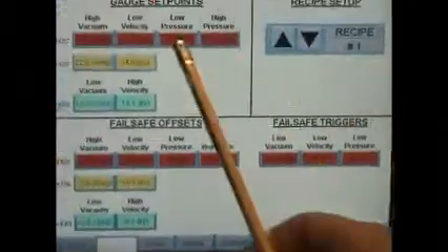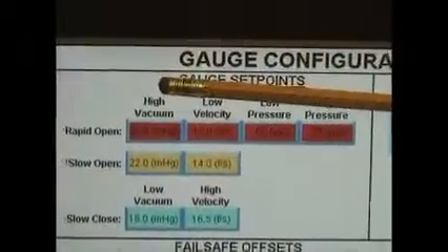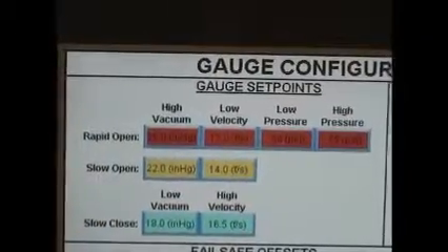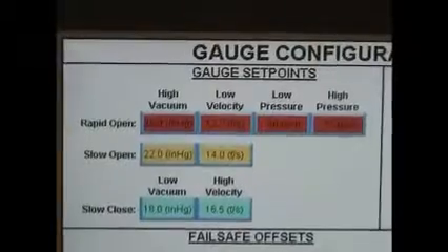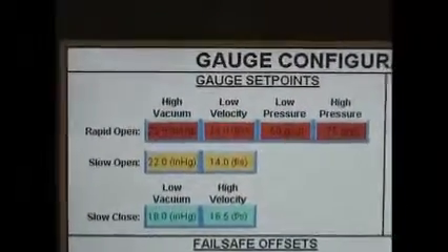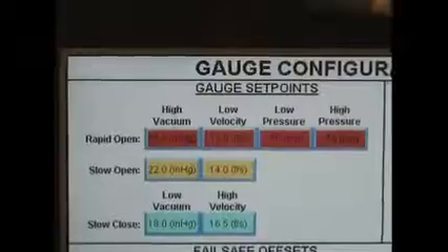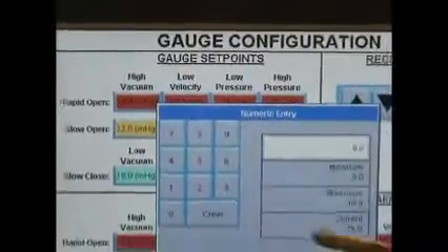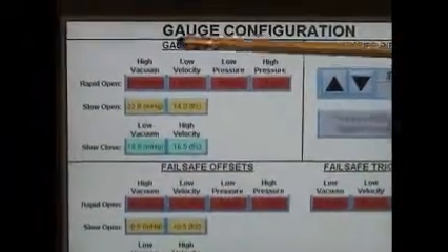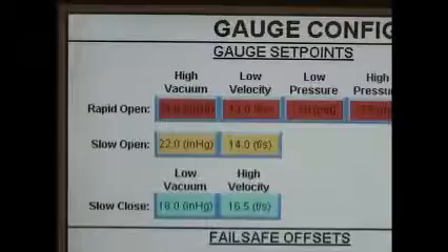First of all, we're going to touch our setup button in the lower right hand corner of the screen, and here are our gauge set points. This first column is our vacuum, so let's focus on our vacuum first. The first item here is our rapid open. This is the vacuum setting that determines the start of our red zone, in other words, our emergency zone. Currently, we have it set at 25 inches of mercury to trigger the valve to open rapidly. Let's say, for example, you want to change it to 24 inches of mercury instead. You simply enter 240, and we have 24. We hit enter.